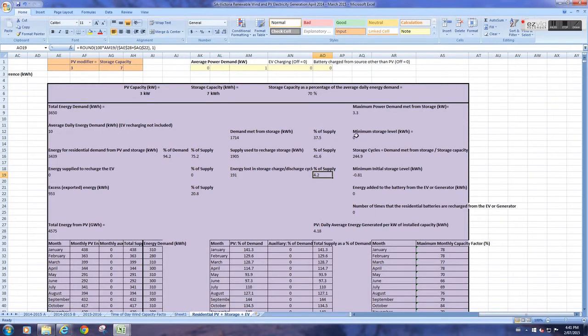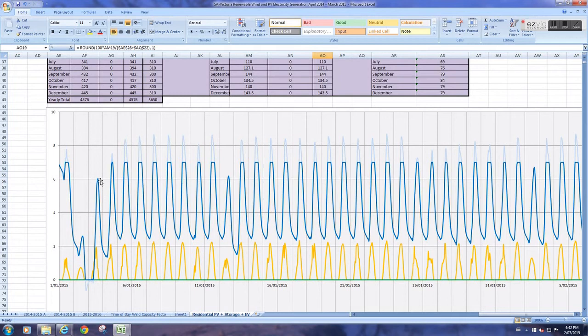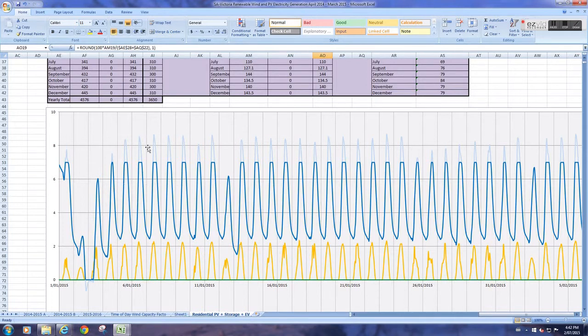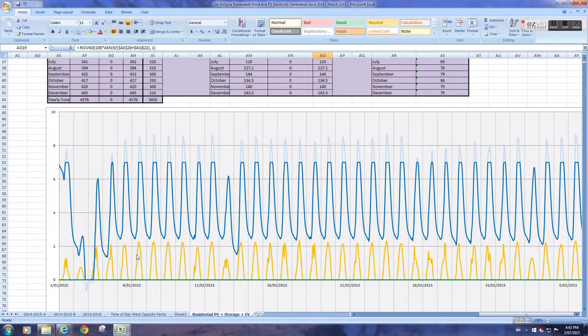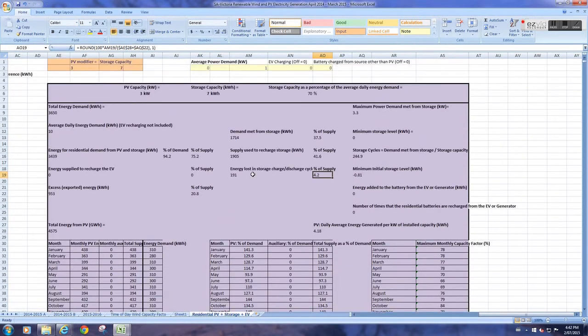Now, the batteries aren't 100% efficient. They lose some energy as they're being charged and discharged. So, for good, decent quality lithium-ion batteries, the type that Tesla are producing, they have about 90% efficiency, so about 10% is being lost. So, this is just showing that you're losing about 10% of the total energy being used to recharge the battery. We're losing 4.2% of supply at 191 kilowatt-hours. It's showing that the battery is being fully discharged at different times of the year. Down here, this is being shown on the graph. So, this period here, the battery was fully discharged, recharges during the day, discharges at night. Recharges during the day, discharges at night. So, this is the battery level in blue. The light blue at the top here is when there's excess power which you'd be exporting to the grid. This is just PV production on each day.